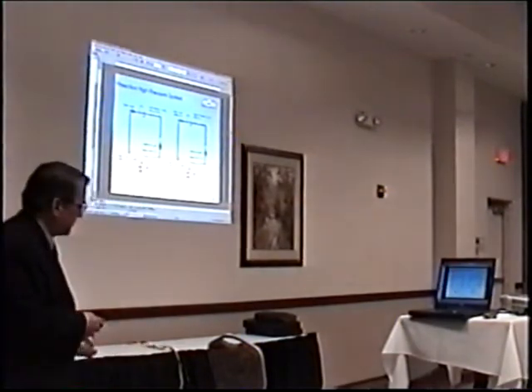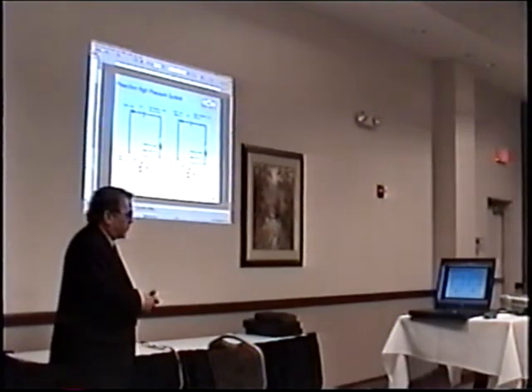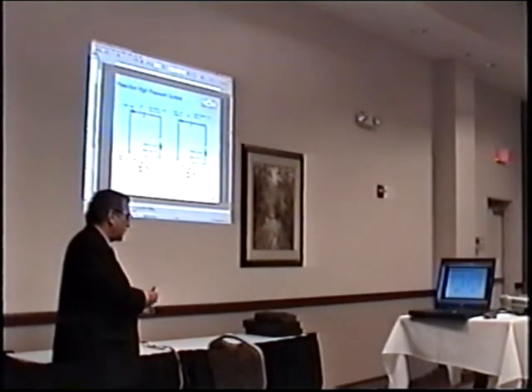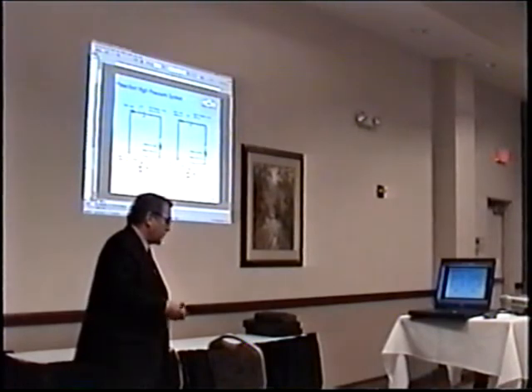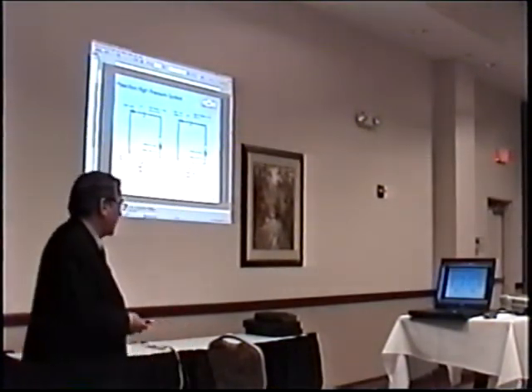And the water mist systems, although it's great, you don't need the electric power perhaps. You would need to run a pump. You don't need an above-ground tank that you would need for sprinklers. With the water mist system, you don't need to perhaps dig a trench because you can have self-contained building units providing, say, 30 minutes of protection inside the building without having to dig a trench in from a common water supply or water tank for sprinklers. Many of those sites you cannot dig in the ground because it's heritage property and you don't know what's in the ground and they won't let you just dig a trench.